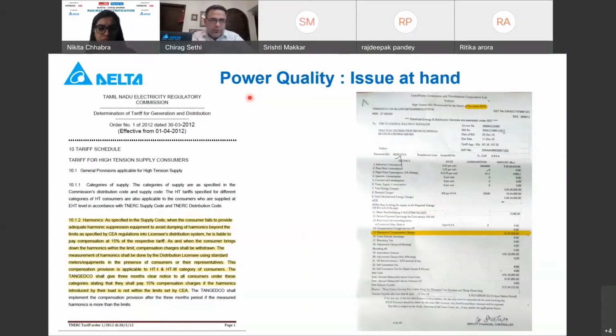Power quality issue. Well, the issue of power factor and harmonics is not new to the various stakeholders who are involved in railway electrification. Traditionally, yes, capacitor banks and series reactors are also being used in various traction substations. Incidentally, they do not meet the requirements which are set by the various electricity authorities as well as the latest standards. What you see here is a notification from Tamil Nadu Electricity Regulatory Commission, which mandates a penalty of 15% of the monthly electricity bill in case the harmonics are not kept within the permissible limits. And the moment these harmonics are brought within the limits, the penalties will be waived off.